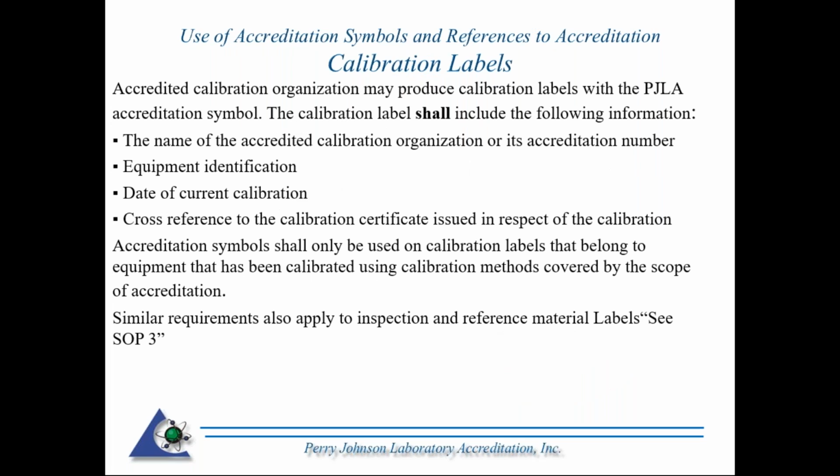Calibration labels. Don't see it too often. Once in a while. I'm a calibration program manager, so I mostly assess calibration organizations. We do have requirements for using the logo on calibration labels. These are the labels where, to give you an example, a pH meter that you send off to the calibration lab, and they put that little sticker on there stating when it was calibrated, and when you desire for the due date, then it specifies the calibration status of the instrument. So that's what we're referring to here.